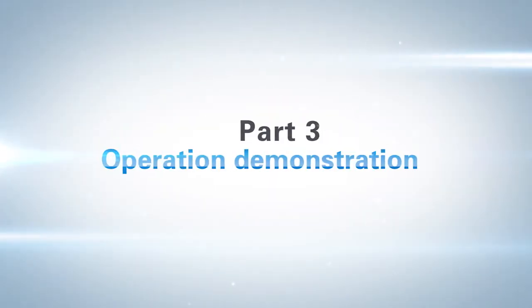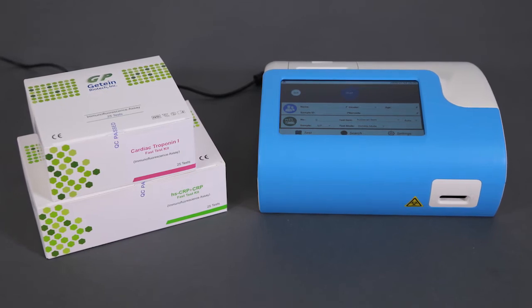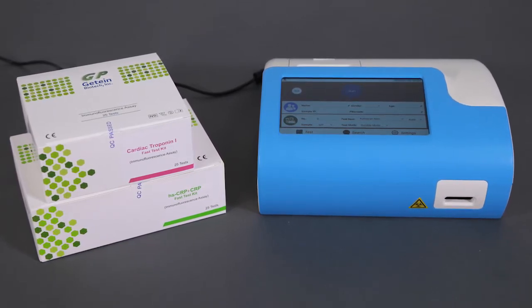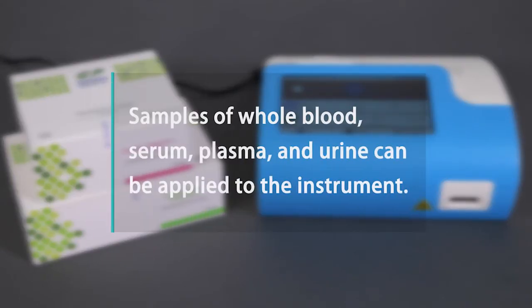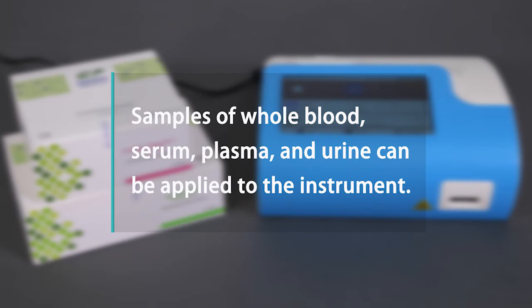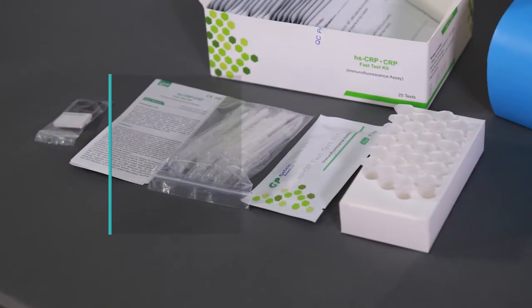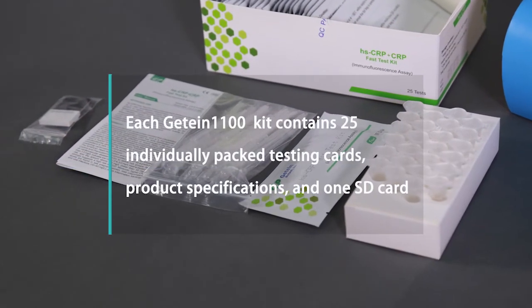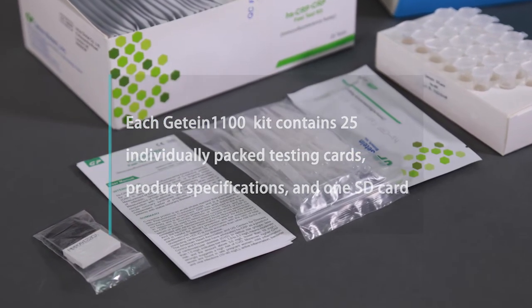Part 3: Operation Demonstration. The Getein1100 Immunofluorescence Quantitative Analyzer shall be used with matched reagent kits as listed in the table below. Samples of whole blood, serum, plasma, and urine can be applied to the instrument. To ensure the accuracy of measurements, please allow 20 minutes of warm-up time before testing. Each Getein1100 kit contains 25 individually packed testing cards, product specifications, and one SD card.